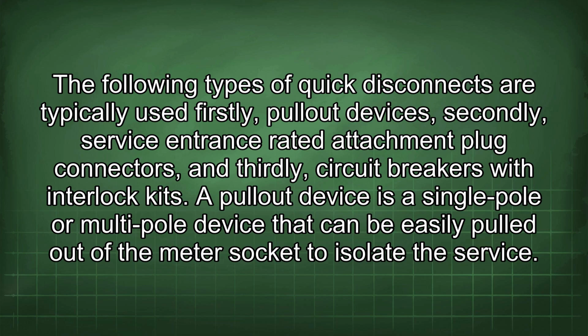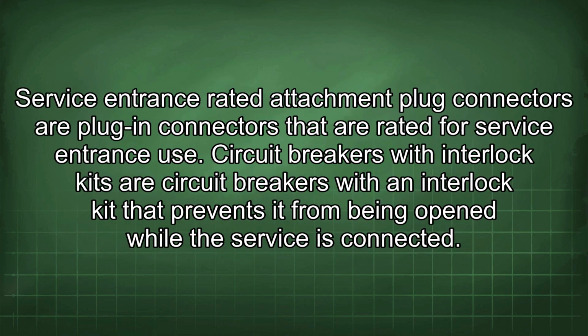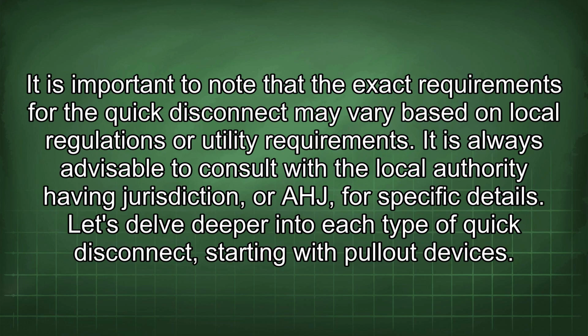A pullout device is a single pole or multi-pole device that can be easily pulled out of the meter socket to isolate the service. Service entrance rated attachment plug connectors are plug-in connectors that are rated for service entrance use. Circuit breakers with interlock kits are circuit breakers with an interlock kit that prevents it from being opened while the service is connected. It is important to note that the exact requirements for the quick disconnect may vary based on local regulations or utility requirements. It is always advisable to consult with the local authority having jurisdiction, or AHJ, for specific details.